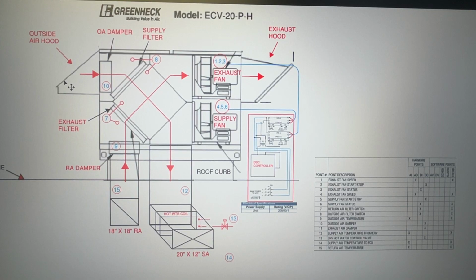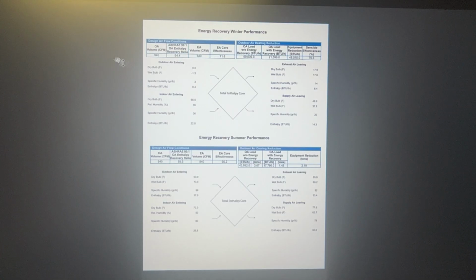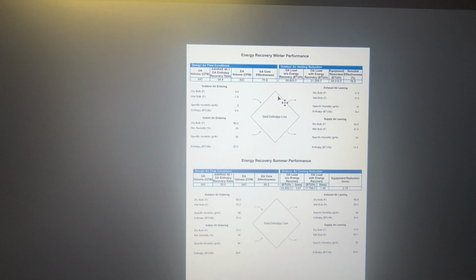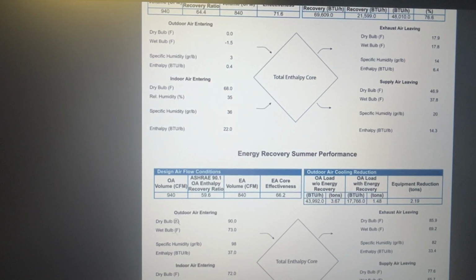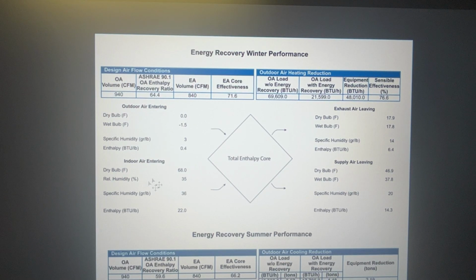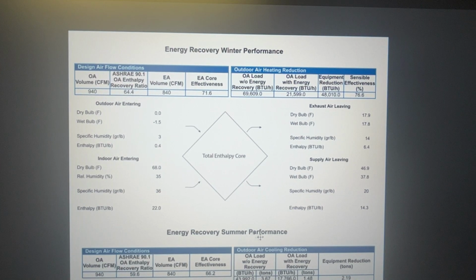I'm going to quickly show the winter versus summer performance chart because I thought it was pretty cool to see how this unit runs depending on the extremes of each time of year that we have here. So this is our winter performance. This is taking a 0-degree temperature. So this is our outside air coming through our core. Our outside air is 0. Our indoor air that we're exhausting is 68. And our supply air leaving is 46. And our exhaust air leaving is 17.